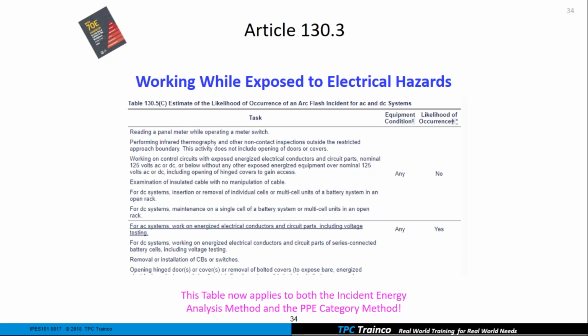And if we come down to the part that's underlined, for AC systems, we work on energized conductors and circuit parts, including voltage testing. So we know we're energized, right? It comes over to the equipment condition, and it doesn't matter if it's brand new or 45 years old. If we look over at the likelihood of occurrence, yes, there is a likelihood of an arc flash because we have covers off, we're testing, and everything's energized. We make one mistake, we have a short circuit or a ground fault, and we are going to be in the middle of an explosion. So this table can be used with either method that we chose to generate our labels with.